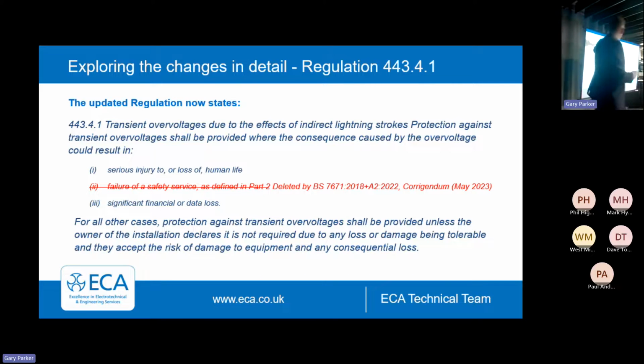These sort of things come from a separate British standard called BS EN 62305 that talks about lightning protection systems. It's massive, 4, maybe 5 sections depending on the extra bit at the bottom, and there's 150 pages that talk about the risk assessment as to whether you need a lightning protection system on its own. I'm fairly sure if you go to somebody like FIRS and ask them to do a lightning risk assessment on your shed, they'd say yes, of course they would.